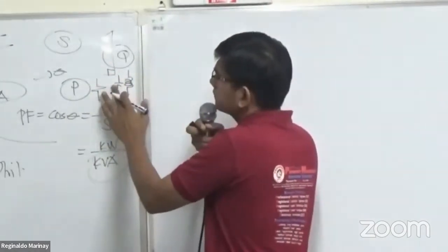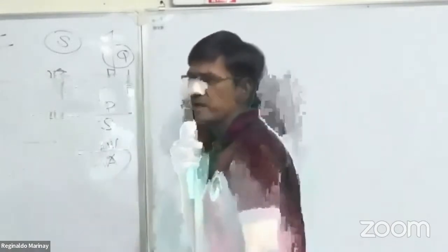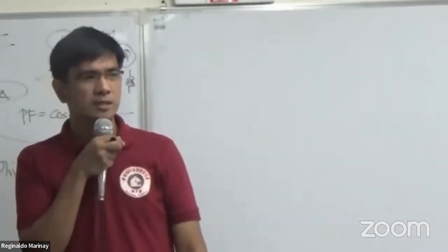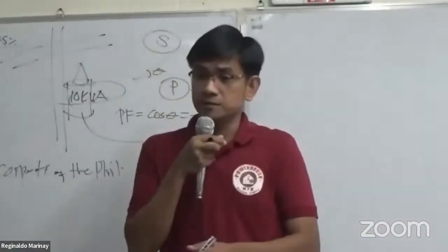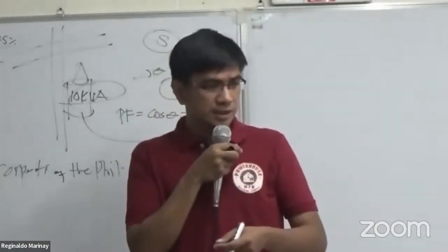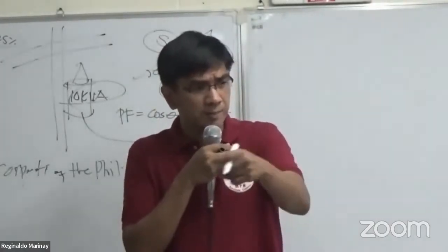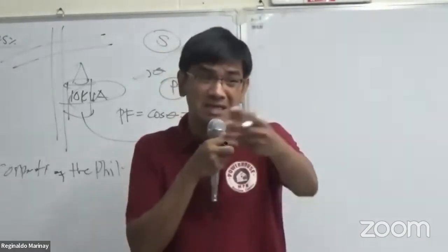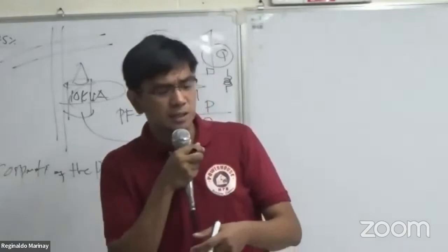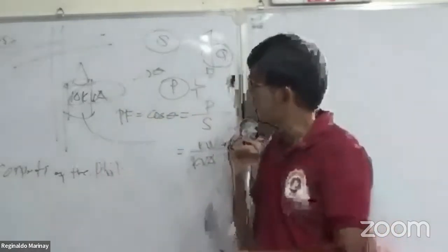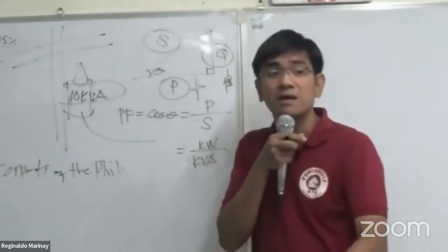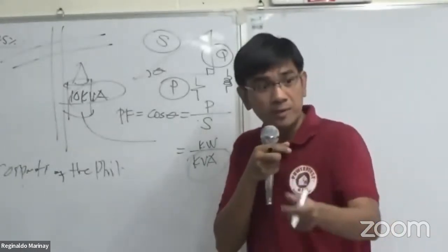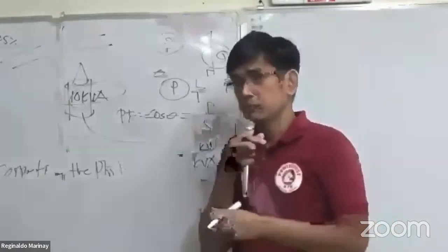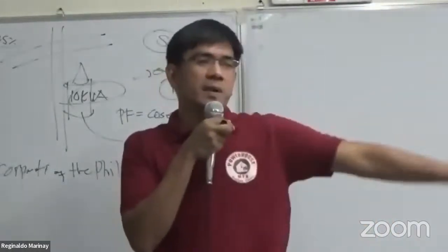Basically, most of our buildings, or I may say all of our buildings, are lacking power factor. Not unless there is overcompensation, meaning there are a lot of capacitor banks so that your power factor will become leading. So in a normal condition, a certain building is inductive, unless you put a lot of capacitor banks. Just take away all the capacitor banks - all buildings are inductive. That's it.